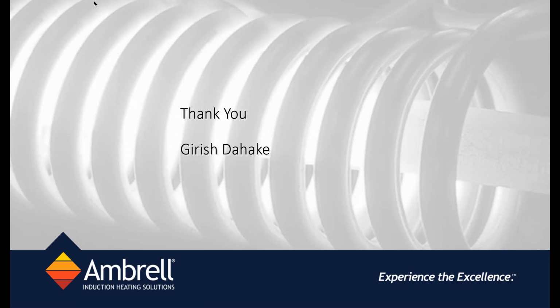Very good question. So I just wanted to absorb all the details of the question to be able to recommend. The size of the metal particles is what is going to determine whether the diameter of the thermocouple wire or the size of the metal particles is larger, because induction heating fields tend to heat based on the size of the metal particles. If there is enough metal particles in the mixture, then you may be able to embed a thermocouple inside your part to measure the temperature. However, like I said, a quick test will let you know if the temperature is a true temperature or a combination of the wire heat as well as the part heat.